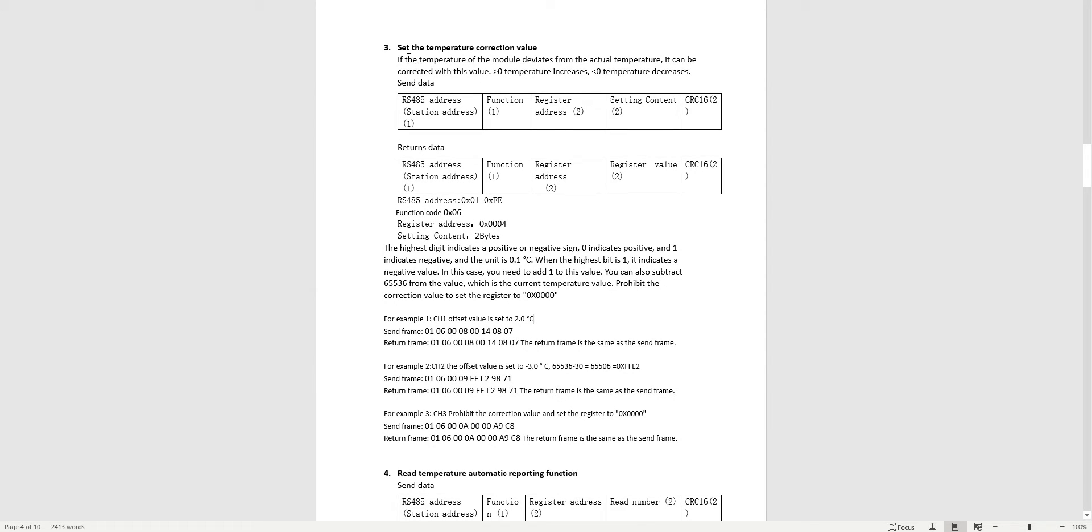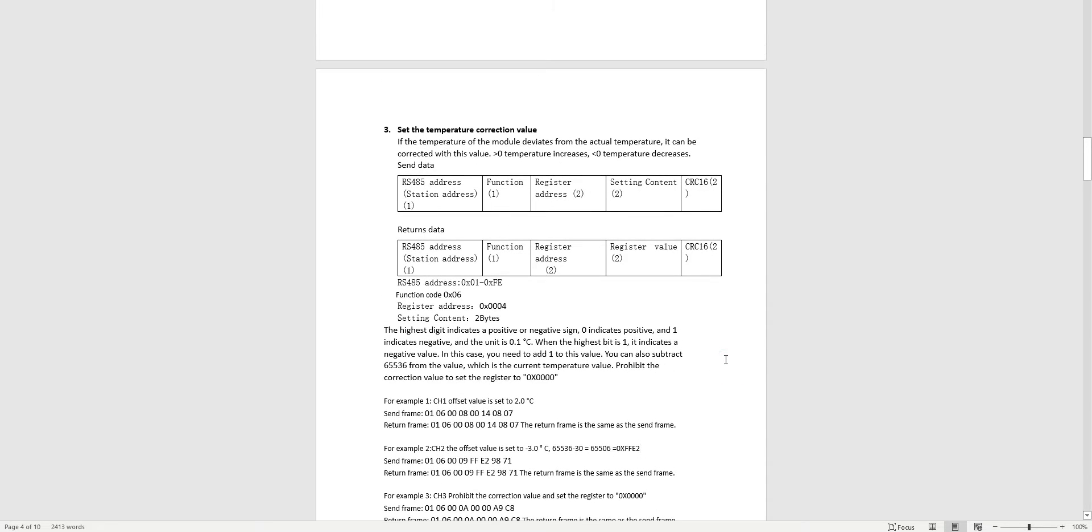This is what the manual suggests. Set the temperature correction value. They say here when you want to subtract from this value, if you want to make minus 3, you need to subtract 30 from this value and then use this number. Like in this example, 65,536 minus 30 is 65,506. So use this value to preset the register and you will get minus 3. If you want to get minus 2, you will minus 20 from this number.